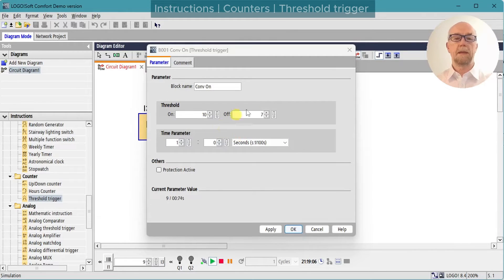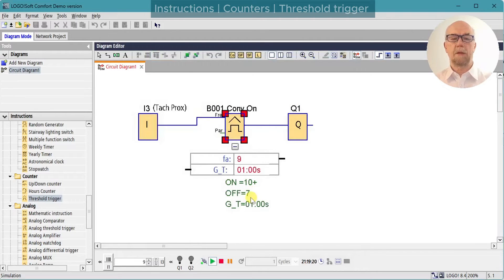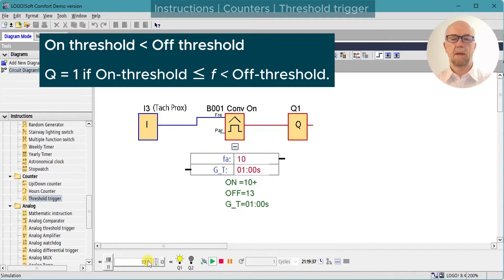We can also set the off threshold at a higher value than the on threshold. Here we've set 10 for on and 13 for off. As we approach 10 it turns on; we keep going — 11, 12 — at 13 it switches off; 14 it remains off. Counting back down: 14, 13 — once we go below 13 it turns on again at 11 and 10, staying on.